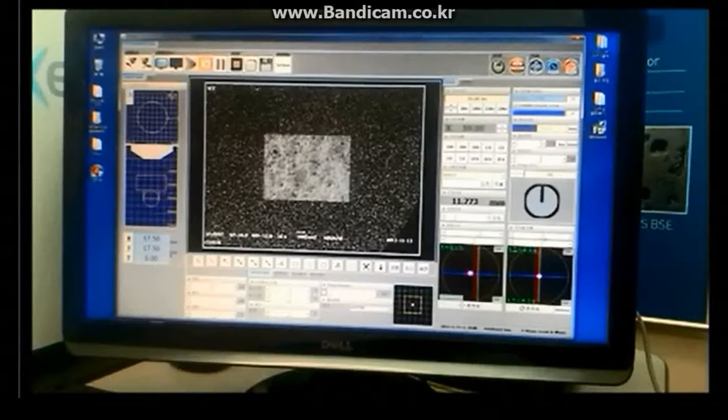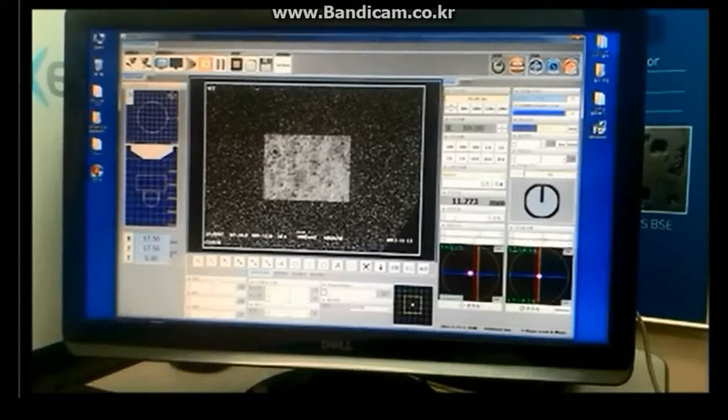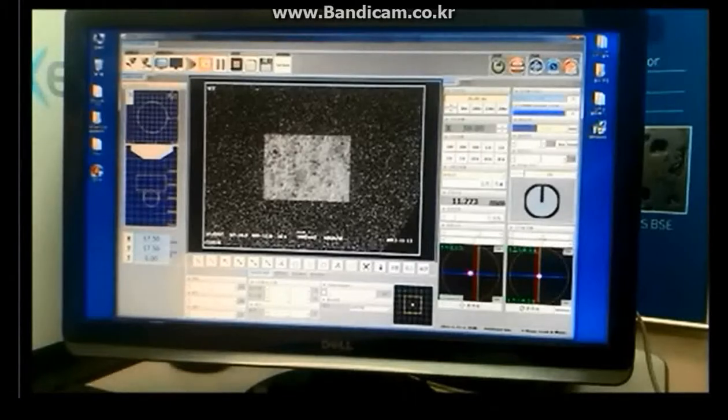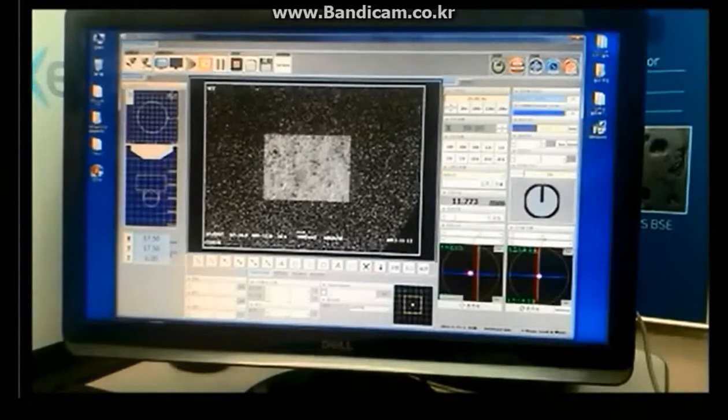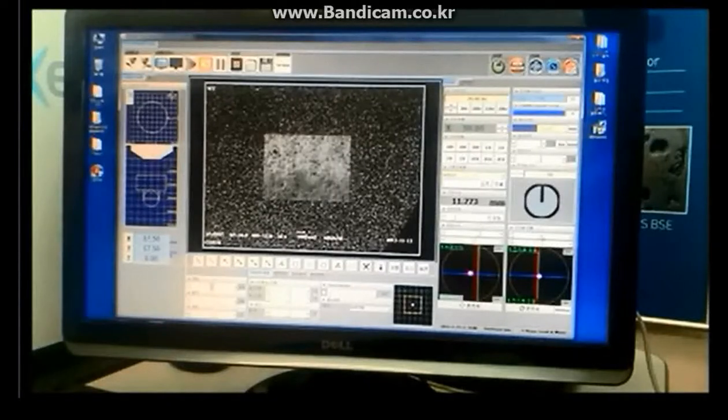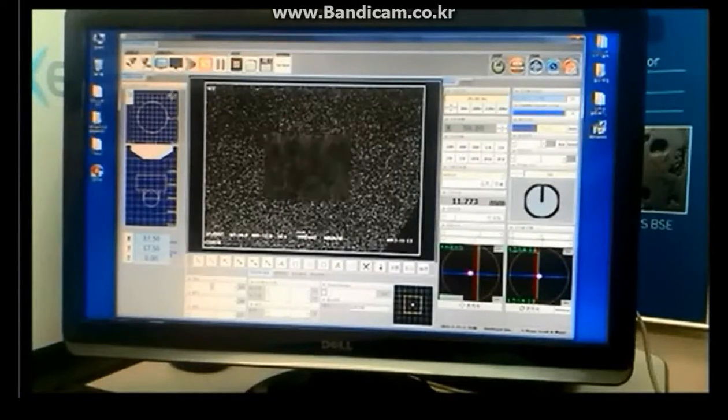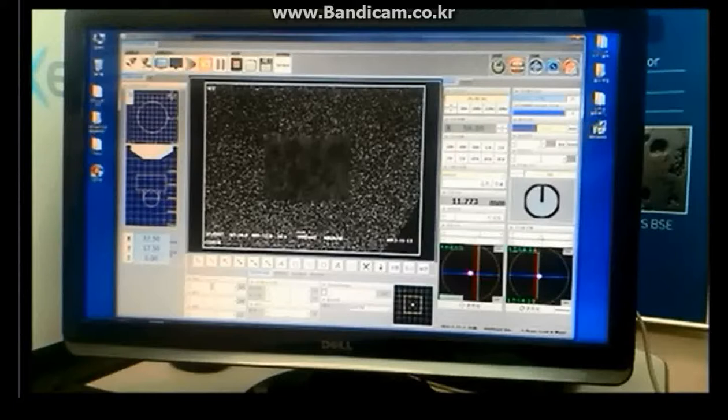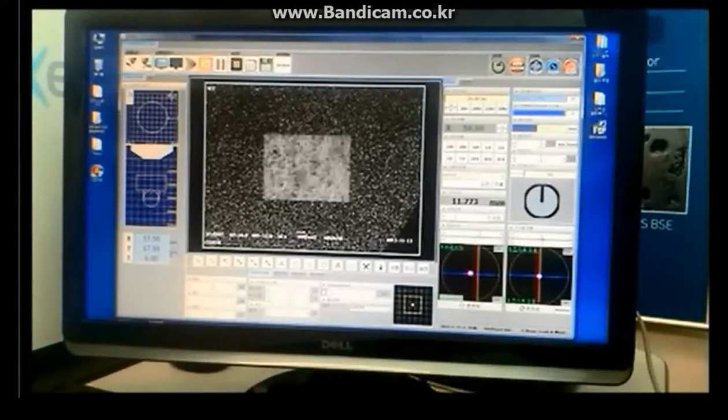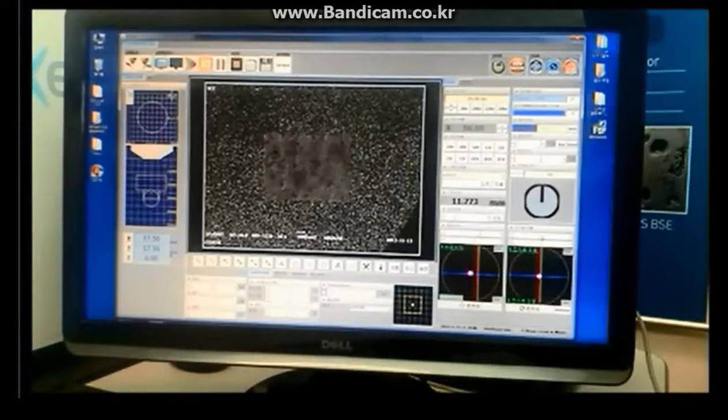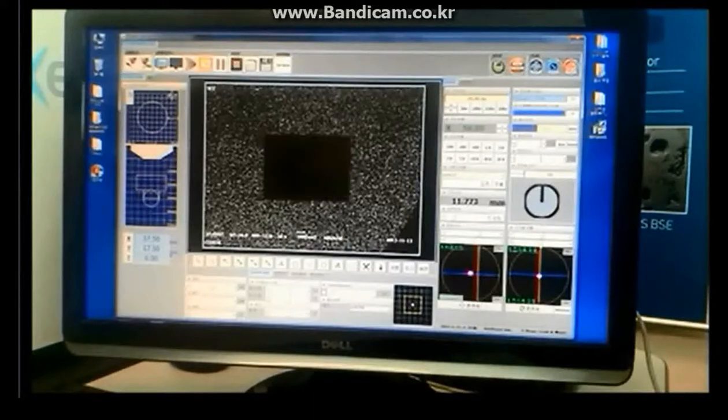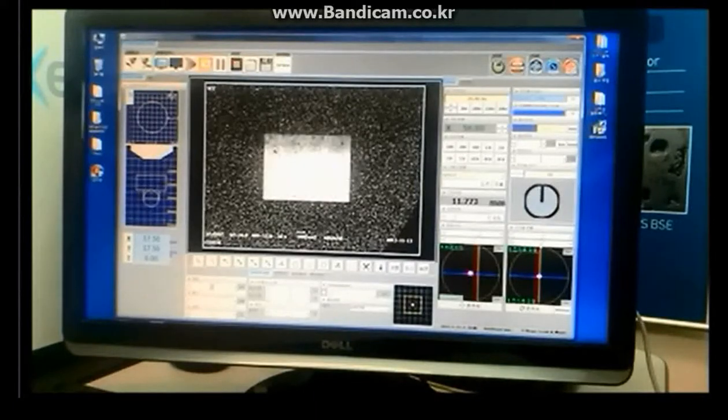Change the x-axis electron gun electron value on the lower right-hand corner of the software to find the brightest location. Change the value for y-axis also.